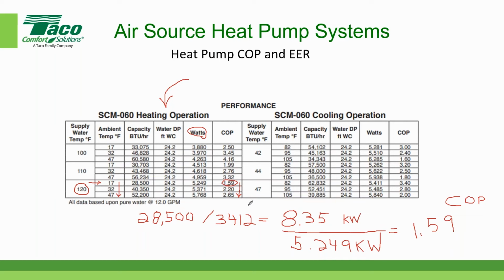Because what we're saying is that when the ambient temperature is 17 degrees out, we get 1.59 times the input. In other words, our output is going to be 1.59 times as much as our input. If we have an ambient temperature of around 32 degrees, you can see that increases significantly. If we have a lower supply water temperature, look what happens: the COP also goes up. So it goes from 1.59, if I'm trying to supply 120 degrees Fahrenheit with an outdoor air temperature of 17, to a significantly higher COP if I'm only trying to generate 100 degrees Fahrenheit at the same outdoor temperature.